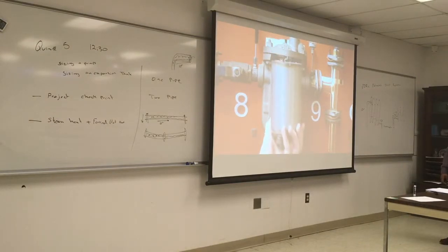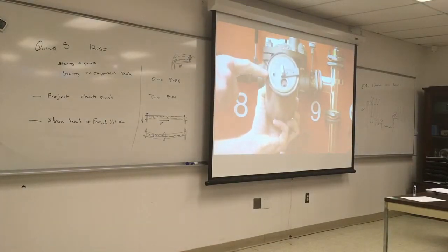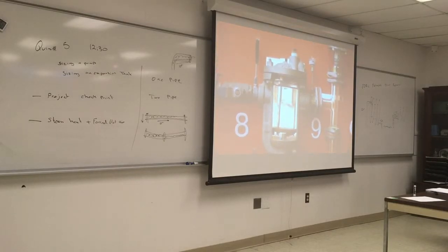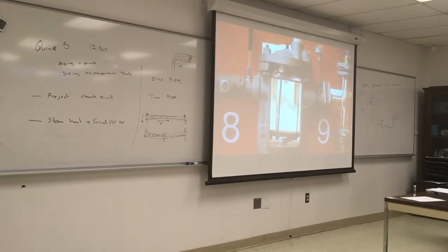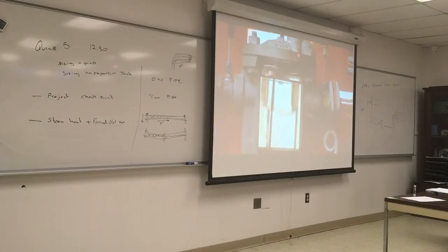It is capable of functioning under very high pressures because the same operating pressure is exerted both inside and outside the bucket. A small orifice called a bucket vent is located at the top of the bucket to ensure that non-condensable gases cannot be trapped inside the bucket. Steam, air, and condensate enter the trap through an inlet tube beneath the bucket. Air and condensate are discharged through an orifice at the top of the trap. At the orifice is a valve that is linked by a lever to the top of the bucket so that the valve is closed when the bucket is in the up position.